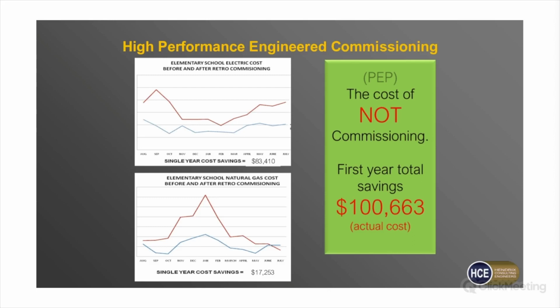After we had a proof of concept there, they went back and checked, and these units had not had the dip switch in the controller set to listen to the control system. So they fixed that. The first year, they saved $83,000 in electricity and about $17,000 in gas, for a total savings of $100,000. Unfortunately, that school had been running like that for about 3 years. So you can see the cost of not commissioning far exceeds whatever it costs to get commissioning done. You can see the before and after graphs - the red is before and the blue is after.